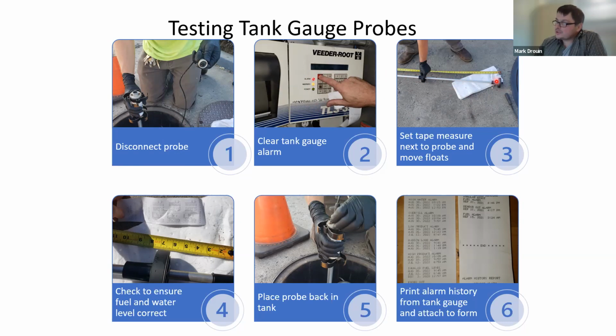And this float right here is your water float. So you have the gas unleaded tank with ethanol, and it starts to phase separate, and you start getting water in there. This float will start to rise up, and it'll tell you have water in that sensor. So you want to clean these floats, move them up and down, and set a little tank tape down there. Then if you look at the PEI document, basically you want to take a measurement of the fuel and the water. I'm not going to go into great detail on that. Your tester should know that. These documents explain it. Please reference the Veeder-Root and the PEI document, but it's a bare minimum.